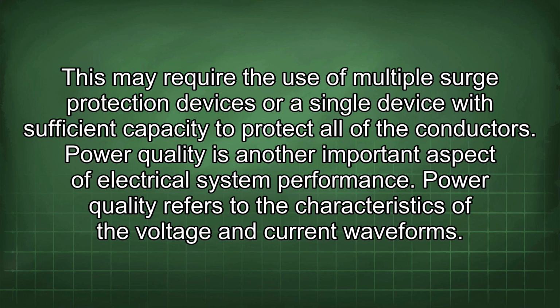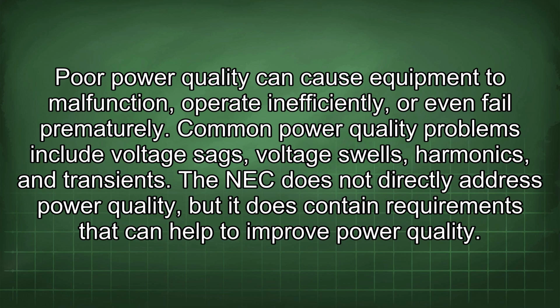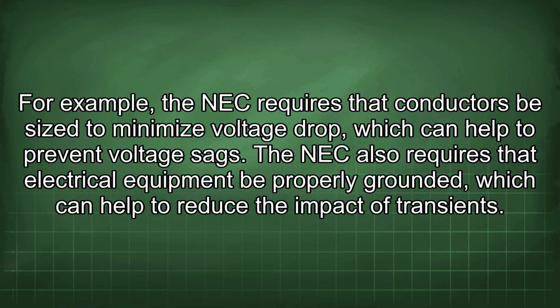Power quality is another important aspect of electrical system performance. Power quality refers to the characteristics of the voltage and current waveform. Poor power quality can cause equipment to malfunction, operate inefficiently, or even fail prematurely. Common power quality problems include voltage sags, voltage swells, harmonics, and transients. The NEC does not directly address power quality, but it does contain requirements that can help to improve power quality. For example, the NEC requires that conductors be sized to minimize voltage drop, which can help to prevent voltage sags. The NEC also requires that electrical equipment be properly grounded, which can help to reduce the impact of transients.